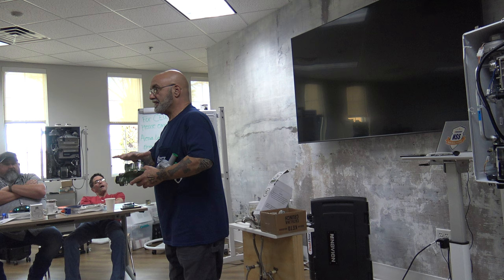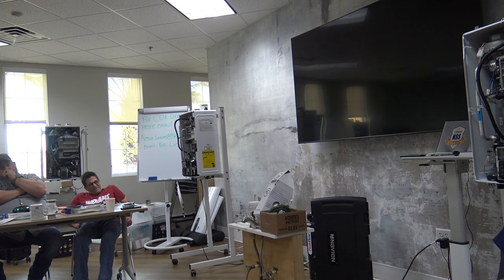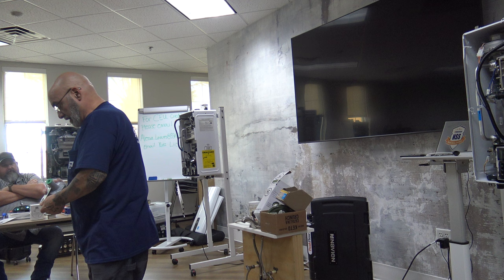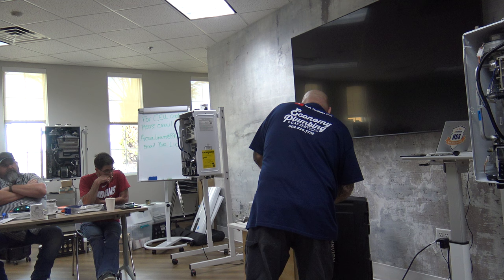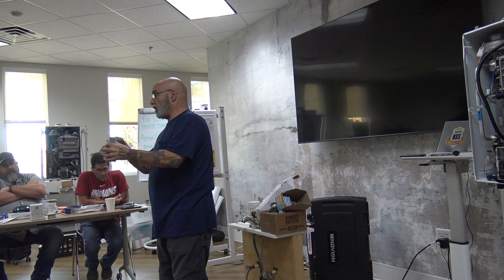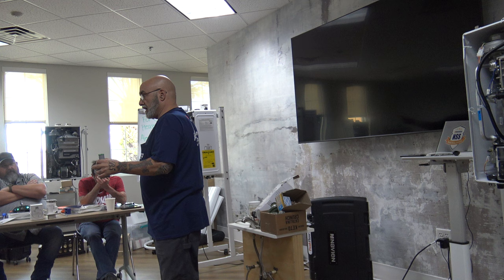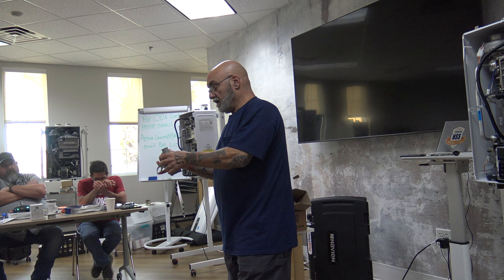This regulator actually has a vent cap on it. But you can remove this vent cap and put what they call a vent limiter on it, but that's for inside the house. I find that installers put this outside the house, not the rain cap. This tiny little hole is what makes it so the regulator doesn't have to be vented outside of a house, but you get bugs in there, tiny little spiders, that will cause the regulator to lock out on bad gas. This vent head, this rain cap, you'll also get critters in there.